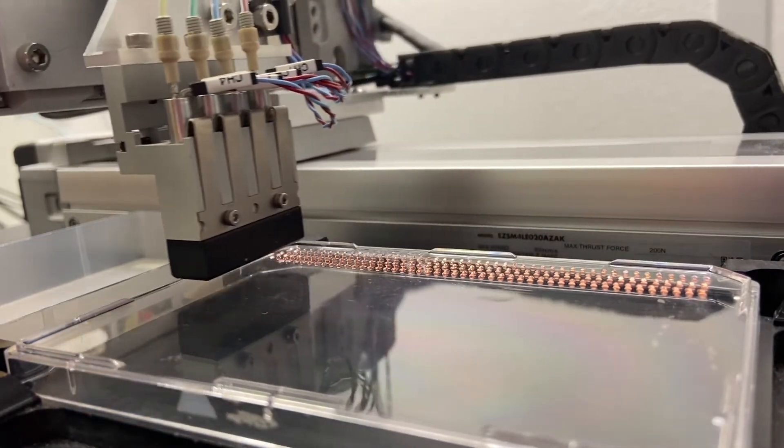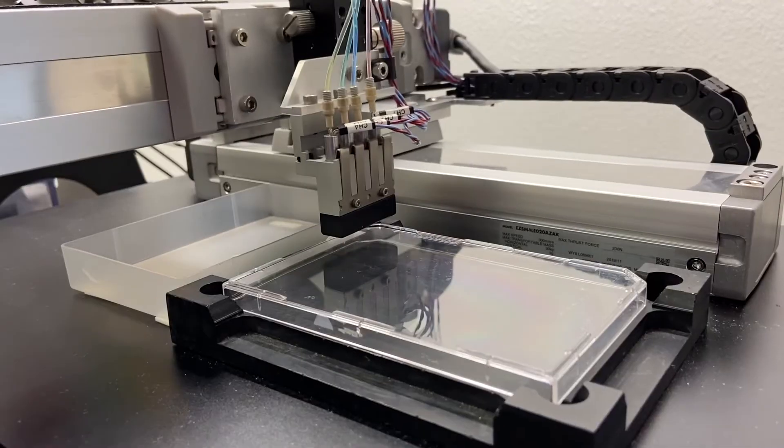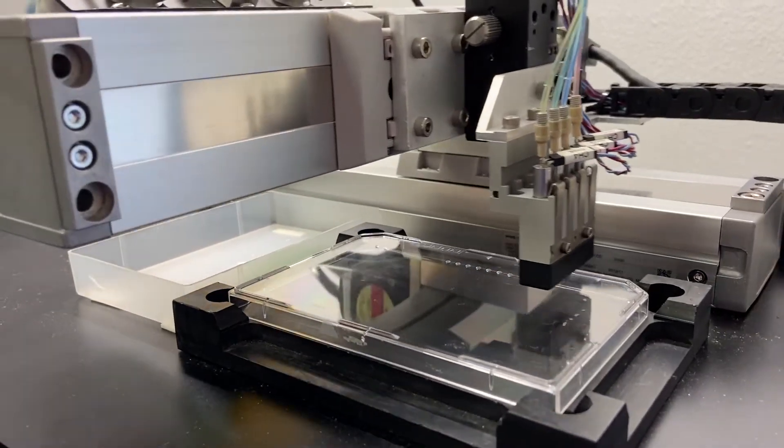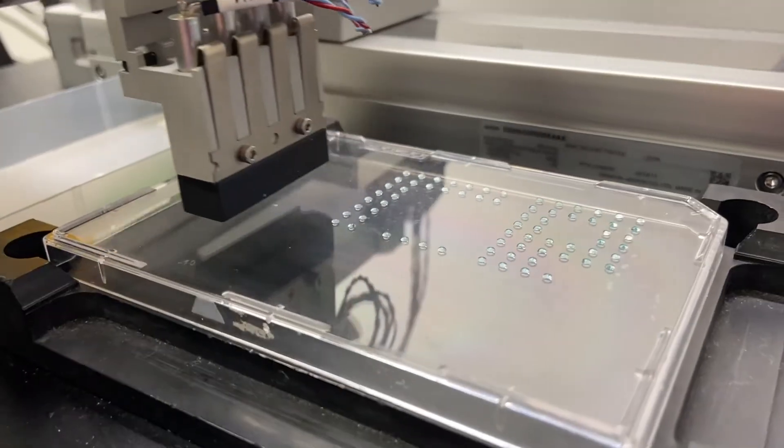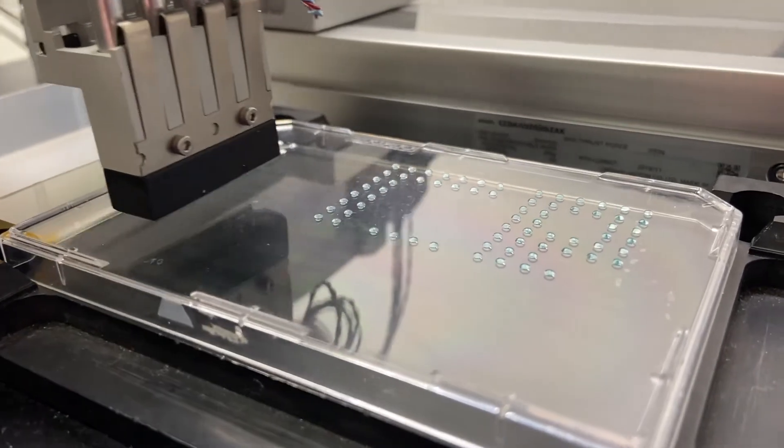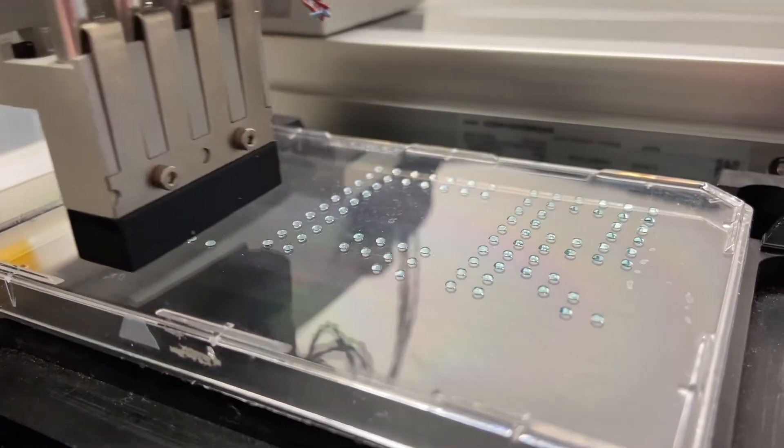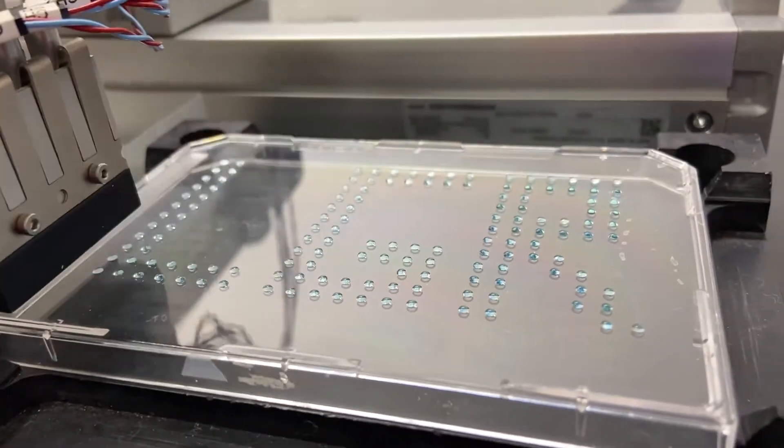The droplet volume ranges from 50 nanoliters to 100 microliters with a full calibration curve, and is also conveniently designed to fit on a small tabletop.